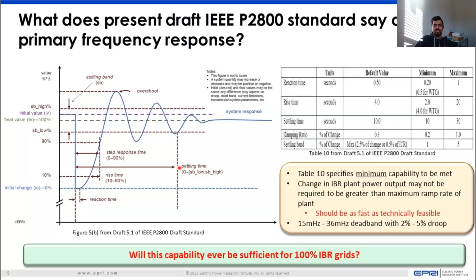So you have these two PV plants, and what we do is to try to mimic the kind of way of evaluating the response of a plant as specified in the draft standard: we introduce a step change in the frequency of this infinite source. So it's a step decrease in the frequency which is appearing on the system end. And we want to see how these IBR plants, with all their control systems, designed in such a way that they have a 17 millihertz deadband and a 5% droop at the inverter level, respond.